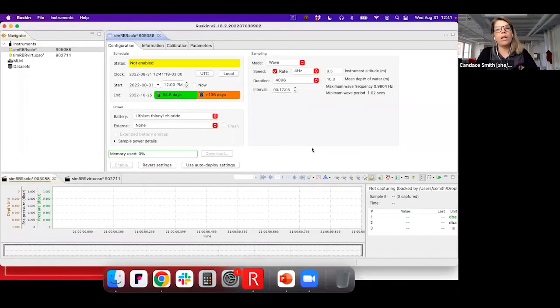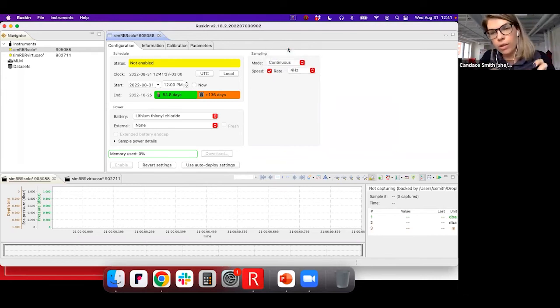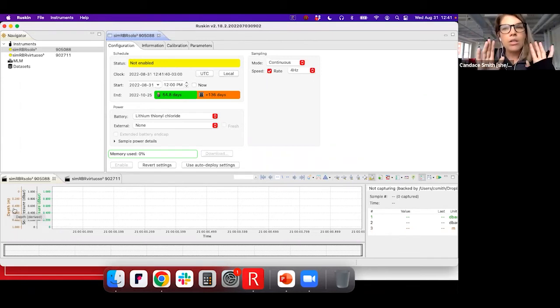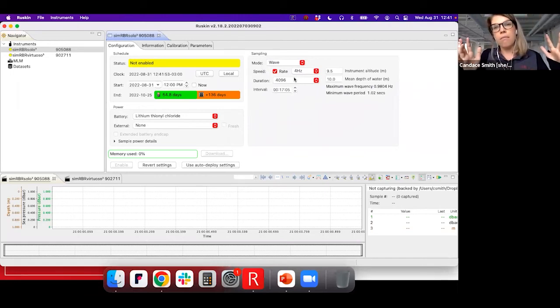Q: Why is using the 1705 trick better than using continuous mode? A: In continuous mode, you're getting pressure, sea pressure — which subtracts atmospheric pressure — and depth, which is derived. Those are three parameters in a continuous time series. When you're operating in wave mode, you also get those parameters plus many, many other parameters.